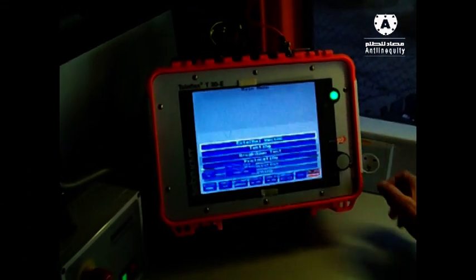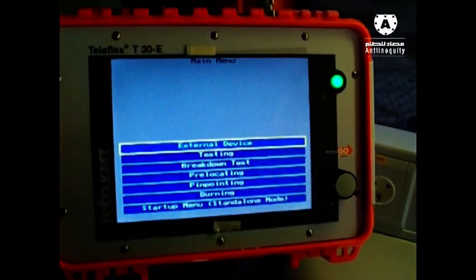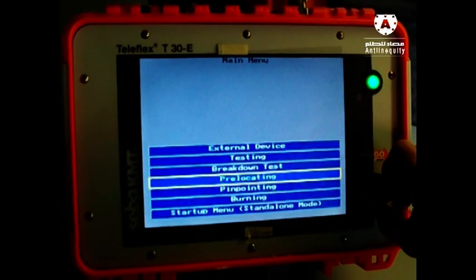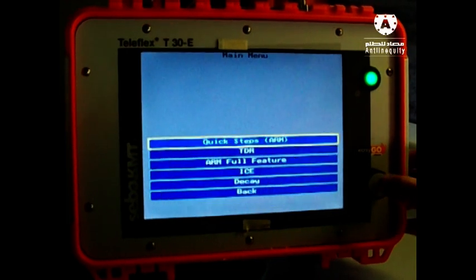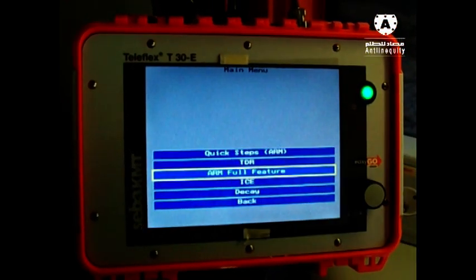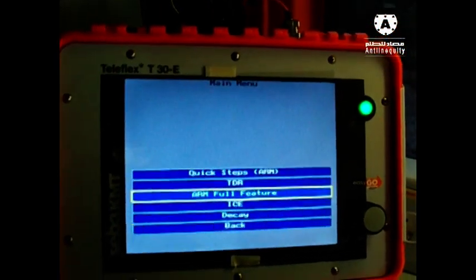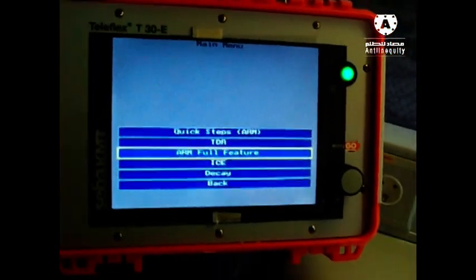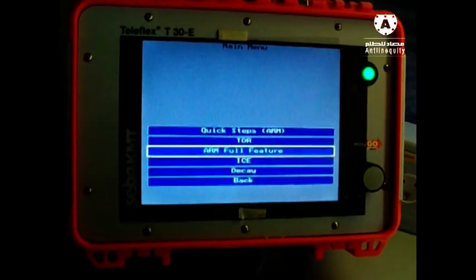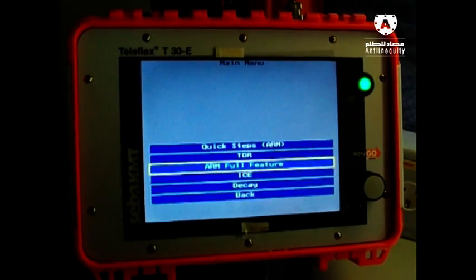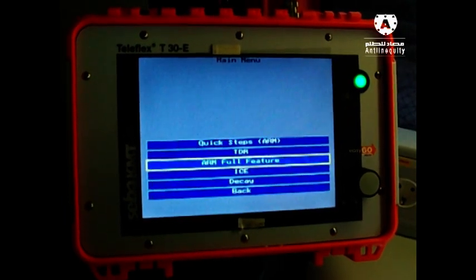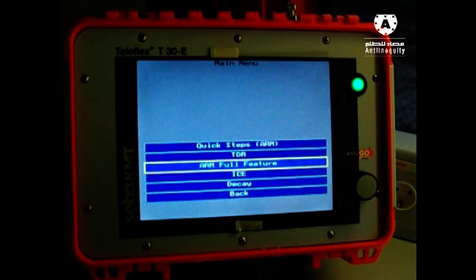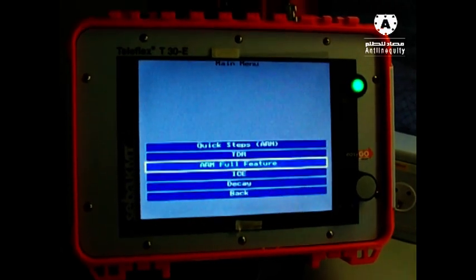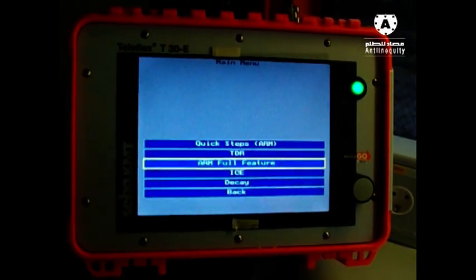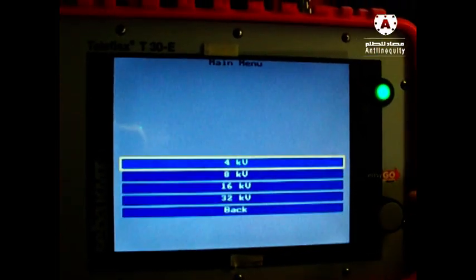This adjustment, I go back to start up. And the next step is pre-location also, but we use now ARM full feature. That means arc reflection mode. We use the TDR to get the picture, and we use a high voltage to get a flashover and to change our high resistance fault into a 0 ohm resistance fault. Okay, let's switch it on.